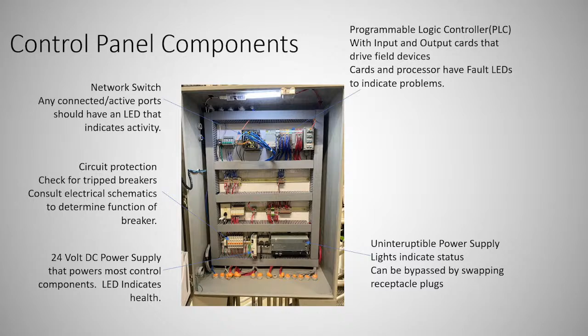Another item to fail is uninterruptible power supply units, UPSs. Basically that's the battery backup. So if you lose power to the cabinet, that UPS is supposed to take over and weather the power outage. And you can see in this cabinet, you generally install these with dual plugs for the UPS. So if the UPS fails, you can just take a plug out of one port and stick it in the other, and you can bypass the UPS. A UPS is also a really typical component to fail, and it's unfortunate because it's supposed to be the component that saves you during power outages, and it takes you out during normal power.